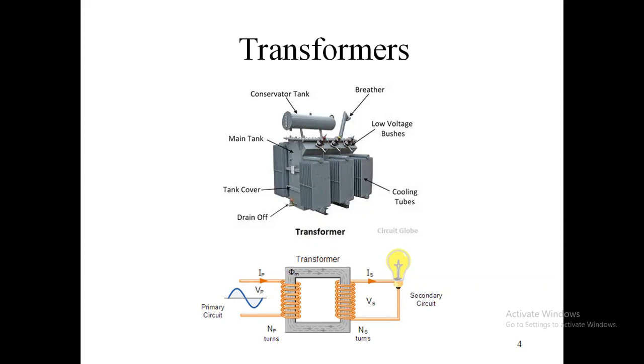On the transmission side, voltage is increased from low to high because we transmit power at high voltage levels. We generate voltages at around 11 kV or 6.6 kV, and we must transmit at higher levels like 440 kV, 765 kV, or 220 kV, so we step up the voltage using a transformer.